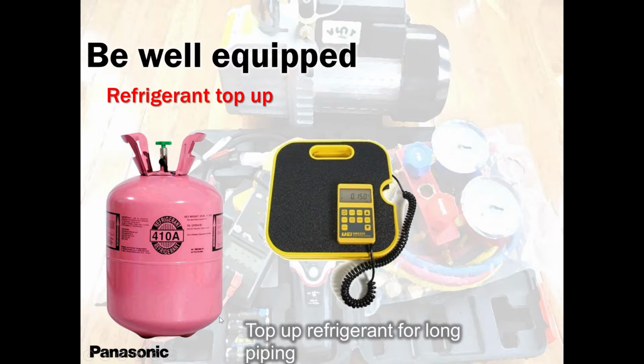Refrigerant, weighing scale. Anytime you have a problem with a system that you are suspicious about refrigerant, the best thing you can do, my friend, I know it will take time, but the best thing to do is recover everything, take it out, re-vacuum, deep vacuum, and weigh in new refrigerant, not the same refrigerant. Okay, please do not use that same refrigerant that you pulled out. I didn't have good results with many job sites, so please put in new refrigerant, liquid, and weigh it in.